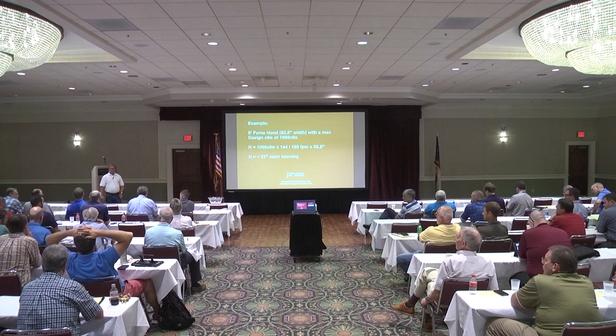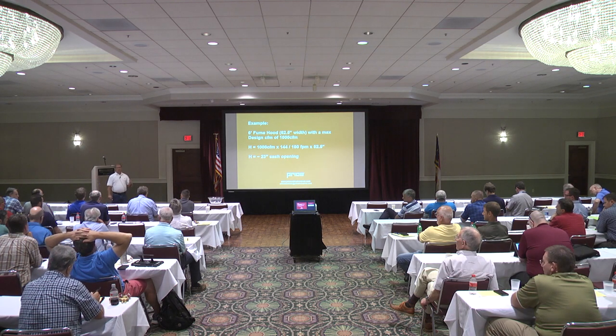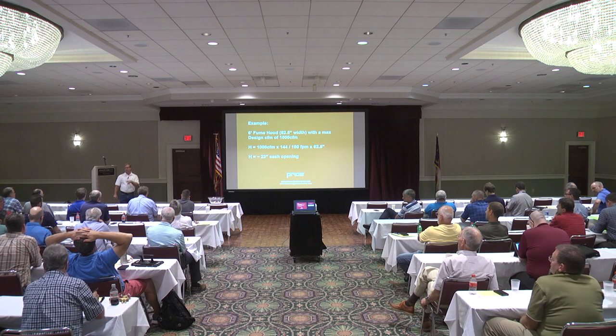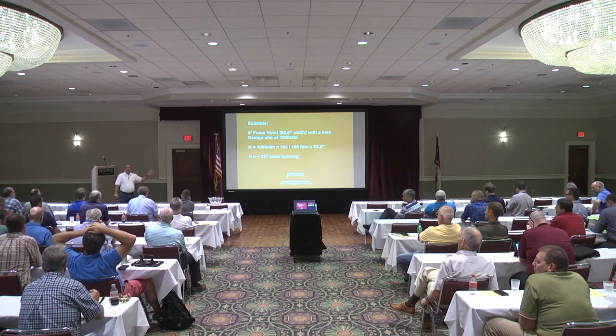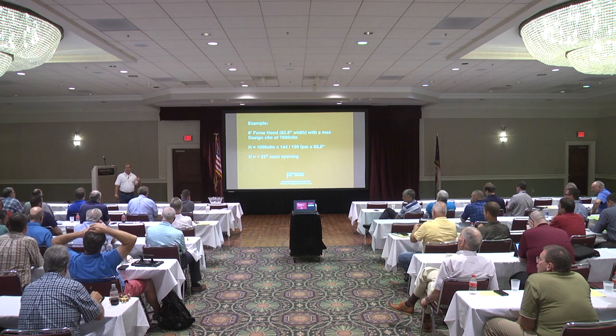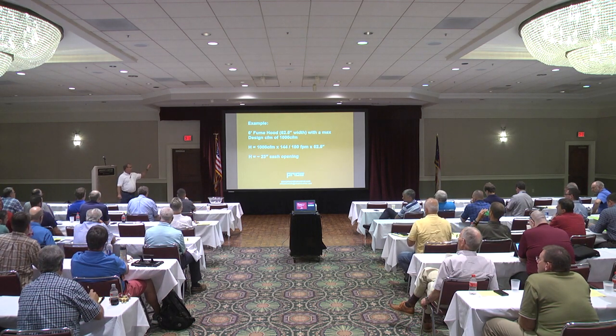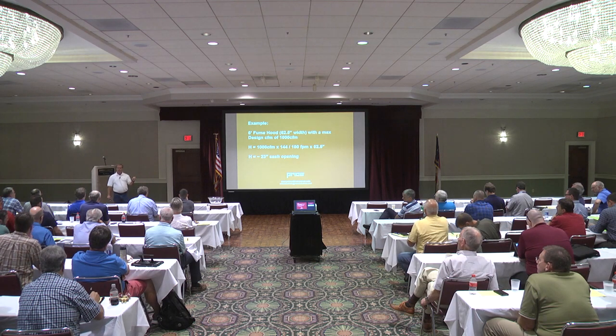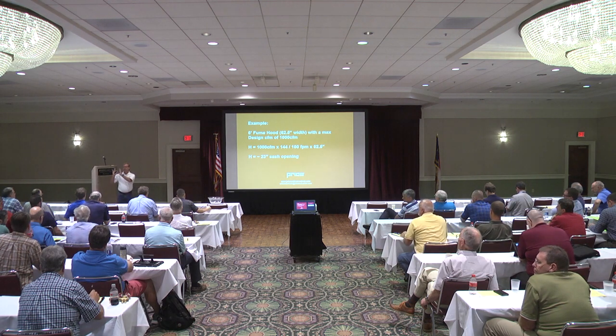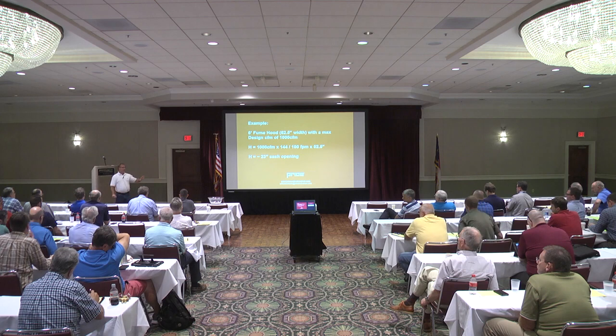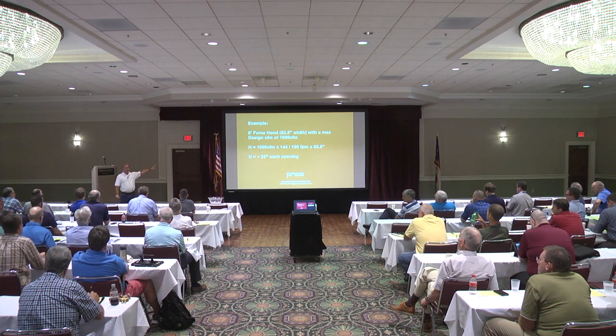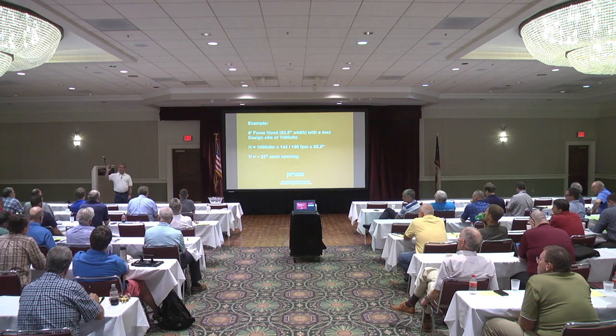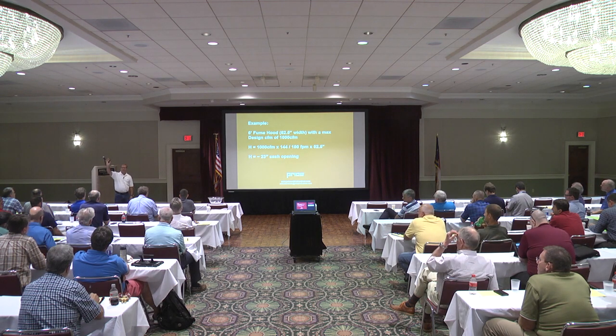You're maximizing the potential, I guess, of that. Well, I'm only trying to satisfy the engineer's design point. It doesn't matter to me what it is. But he's told me that fume hood maximum is 1,000 CFM. And so to take this conversation further, if you're trying to balance the entire lab, and this fume hood is supposed to do 1,000 CFM at maximum, if you don't put that at 1,000 CFM, your supply valve, or your supply air device, is not going to open to its maximum, because it's expecting to see 1,000 to drive it to where it wants to be.